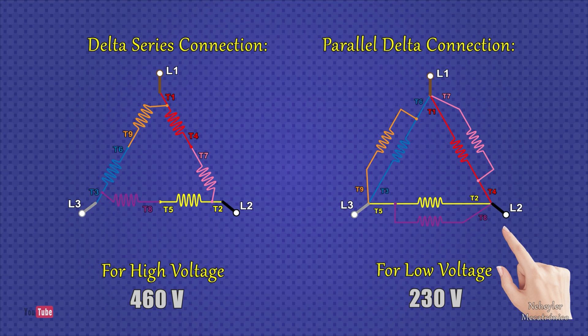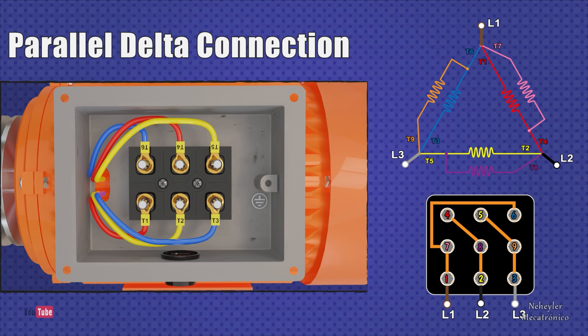Now let's look at the parallel delta connection type. In this case, there is a slight change in the position of the terminals from 1 to 6. In front of Terminal 1 is Terminal 6, in front of Terminal 2 is Terminal 4, and in front of Terminal 3 is Terminal 5. It has been arranged in such an order so that it is possible to use metal plates.